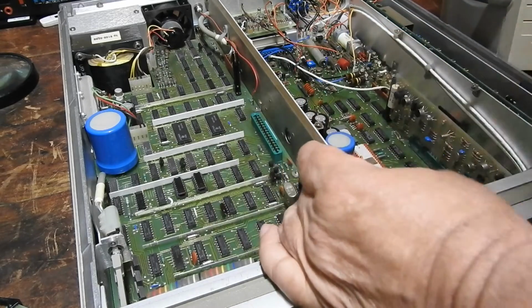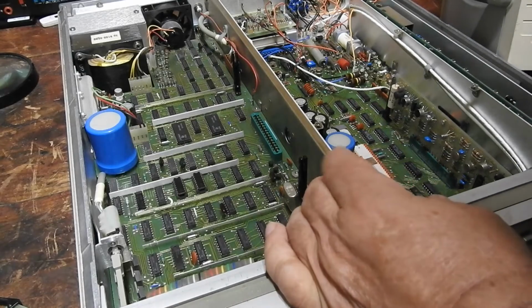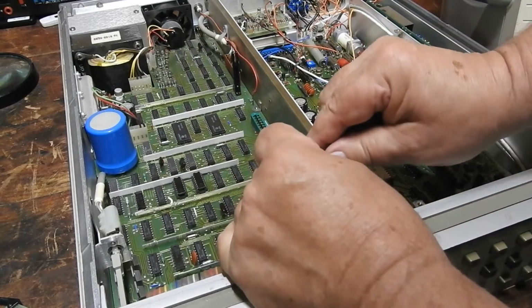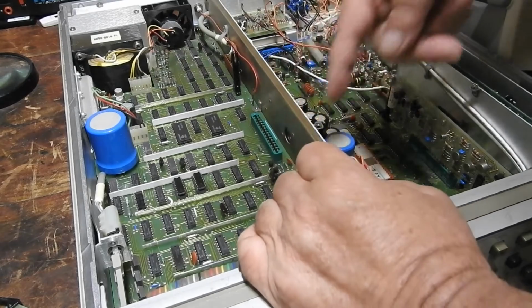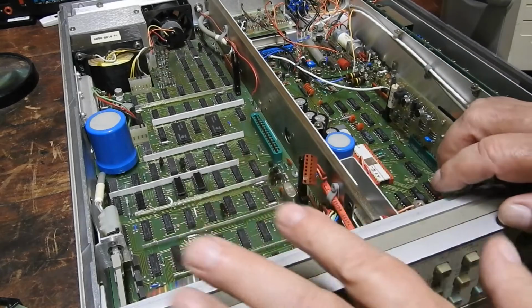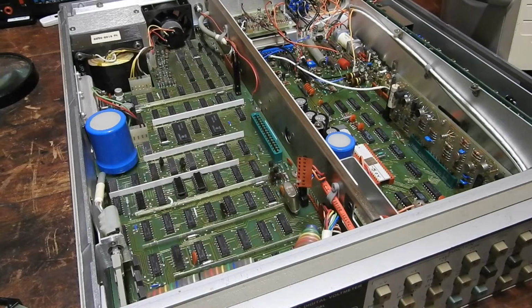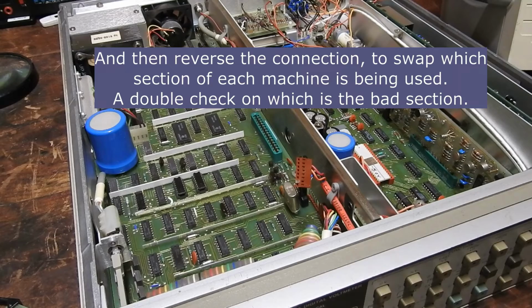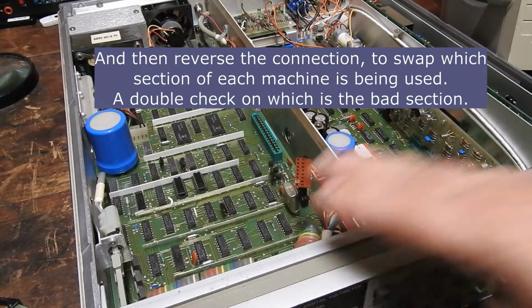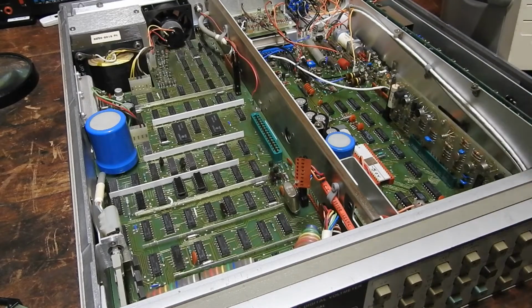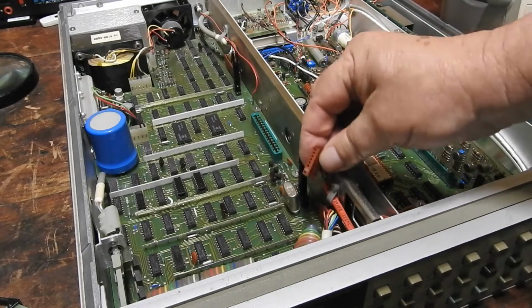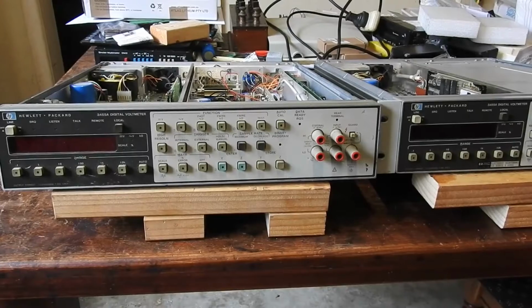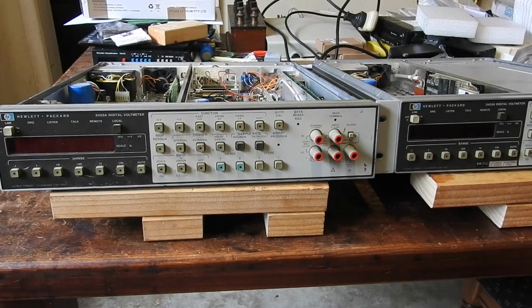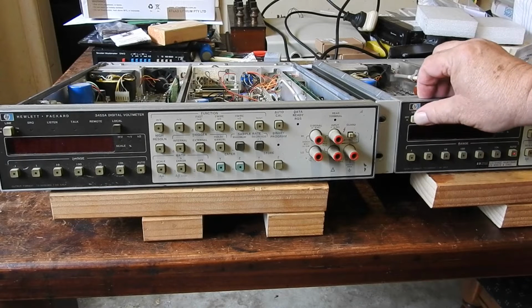What you do is you get a Hewlett-Packard service cable, but I can make one pretty easily. It's just 8 connectors, or 8-pin connector with one of them blocked off. You connect that on one machine to this on the other, and that way you're using the outguard from one and the in-guard from another, and see where the fault goes, if it's still in one machine or it goes to the other. By that means you can determine whether the in-guard or the outguard is failing, and because the troubleshooting steps require you to know which part is no good. Next thing I have to do is make up a little cable to do that. Right, here we have the two 3455s, the one that works.